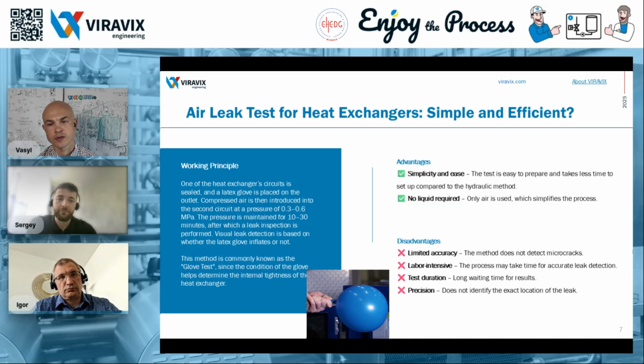All right, Igor, a question for you. When comparing the air method, using air as the testing medium, with the hydraulic one, what are the key differences or things to keep in mind? What types of damage does the air test allow us to detect? I know there are more advanced versions of the air test. Could you briefly comment, in your opinion, what's the real difference? Are there any actual advantages of using air instead of hydraulic testing? From the user's point of view, I don't actually see much of a difference between hydraulic and air testing. As you rightly said, instead of a glove, you can use a pressure gauge, a manometer, which lets you detect even slight pressure changes more clearly and in a smaller range. That definitely boosts accuracy.